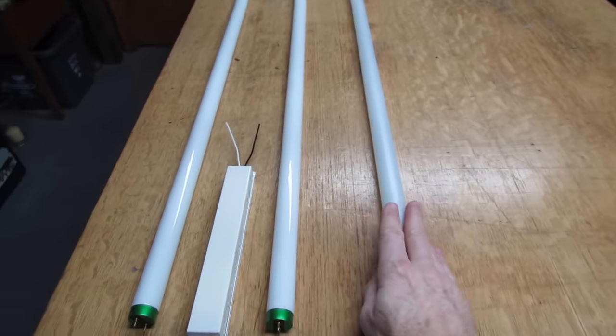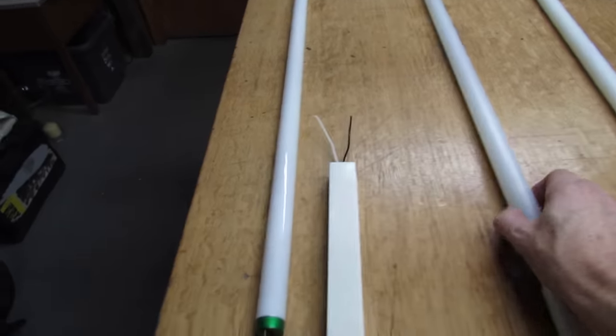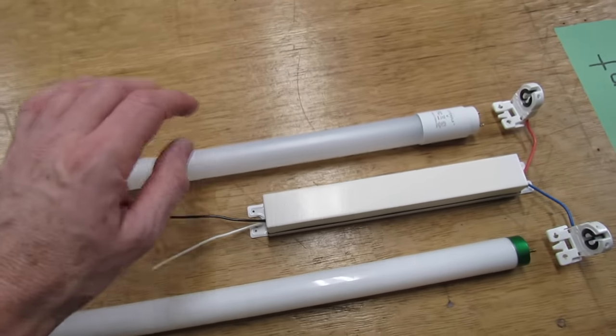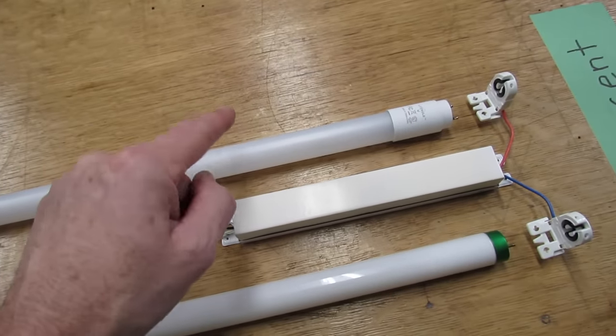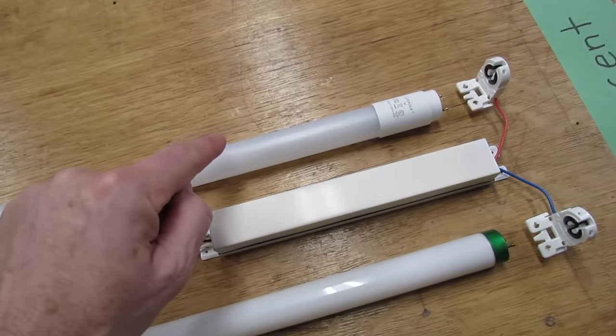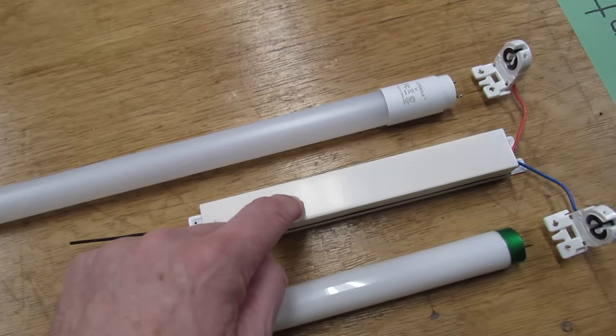If you go with LED plug-and-play, all you do is take out the fluorescent bulb and replace it with the plug-and-play. That's easy, but there are two things to consider. You're using more power because you have to power the ballast and the bulb. Second, if the ballast ever goes, you still have to replace it.